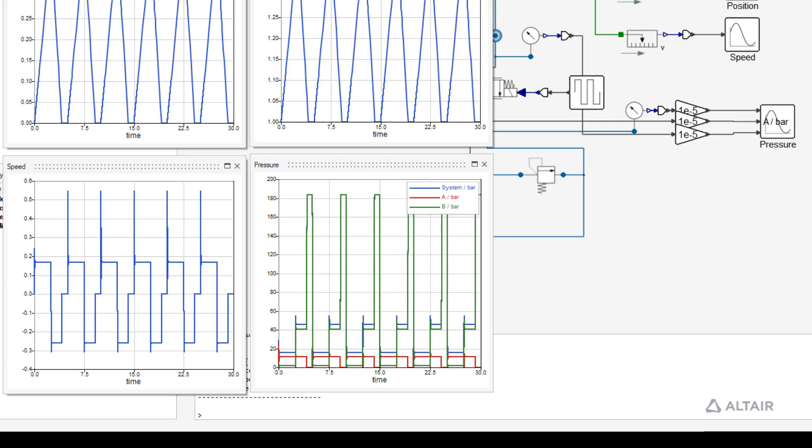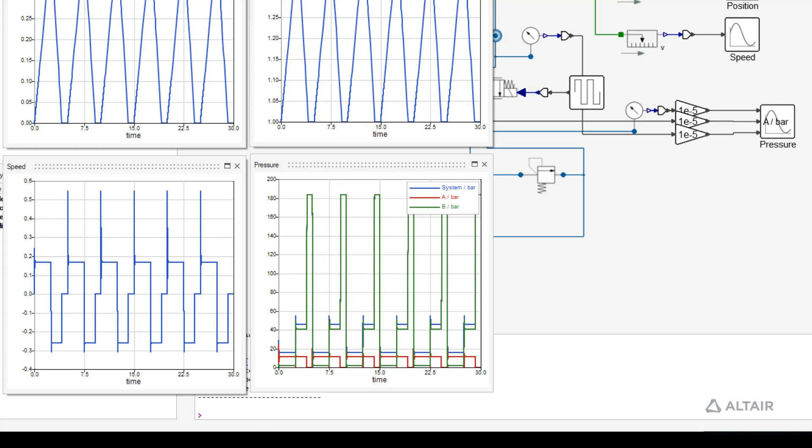But why do we have such a high system pressure? Well, due to the faster retracting speed, the cylinder reaches the end stop before the valve switches to the other direction. Hence, the pump delivers oil into a fixed volume and the pressure rises fast. The maximum pressure is limited by the pressure relief valve. The opening pressure was set to 180 bar. But due to the characteristic of the valve, the system pressure rises up to 185 bar.